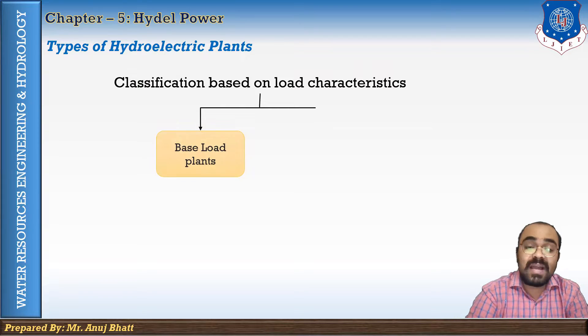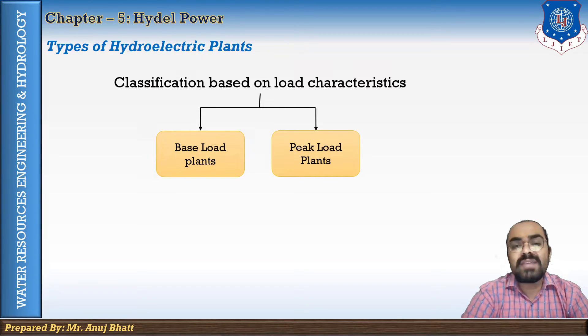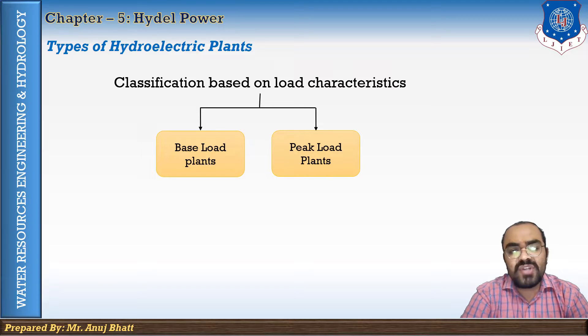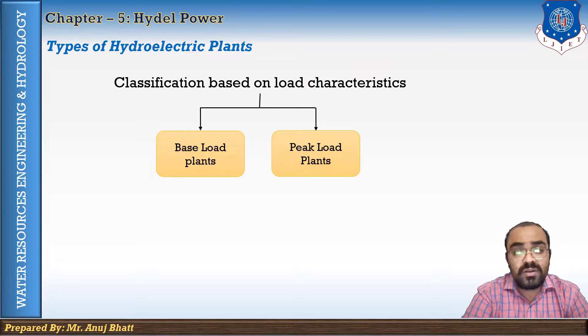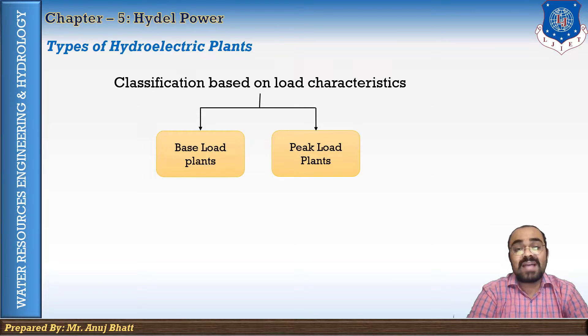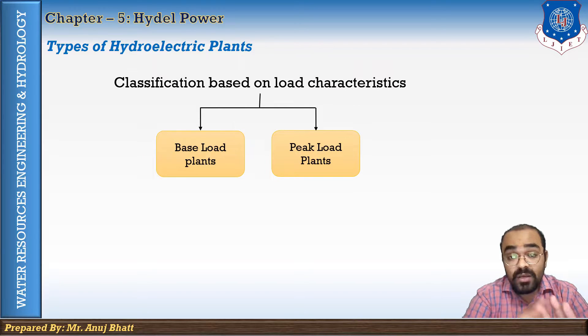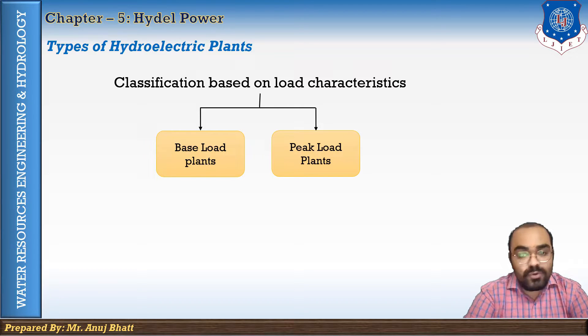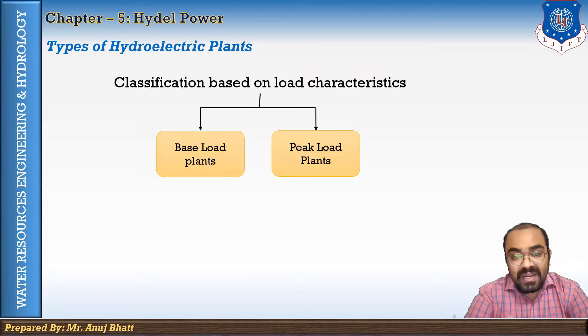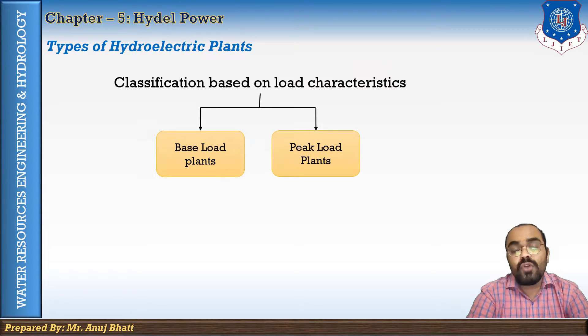The second classification is based on load characteristics: base load plants and peak load plants. Base load plants are those capable of supplying continuous power to the system throughout the year. Both run-of-river plants and storage plants can be used as base load plants. When run-of-river plants without pondage are used as base load plants, their full plant discharge is seldom more than the minimum flow of the river.